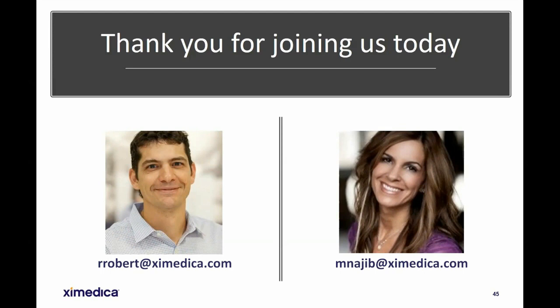Here at Ximedica, we have a very robust quality system. We've launched devices ranging from molecular diagnostics to implantable systems to connected health devices. And the way that we have tuned our quality system to be flexible enough to meet all those different types of devices, as well as rigorous enough to not forget things or miss certain aspects that are going to be important for your design history file, is all done through the quality service agreement we have with each client. And that basically is a checklist that we go through.